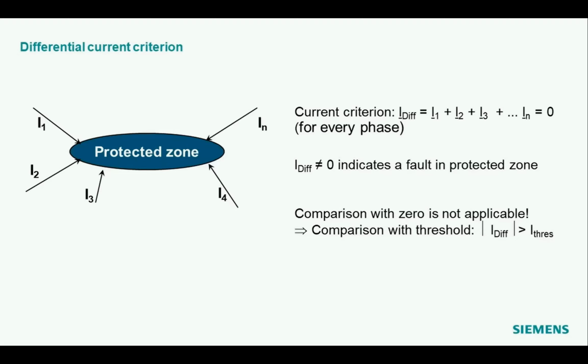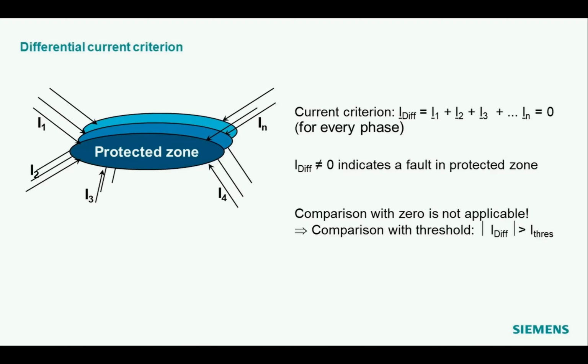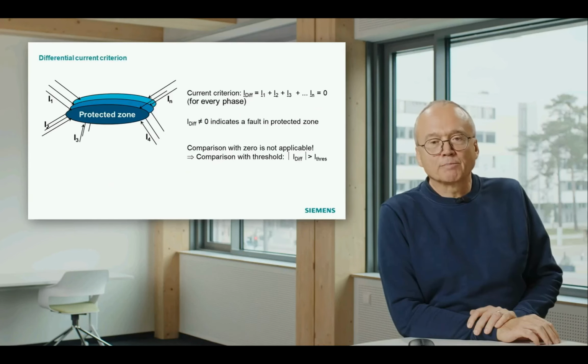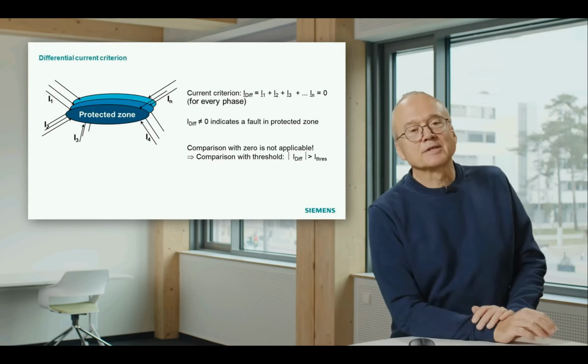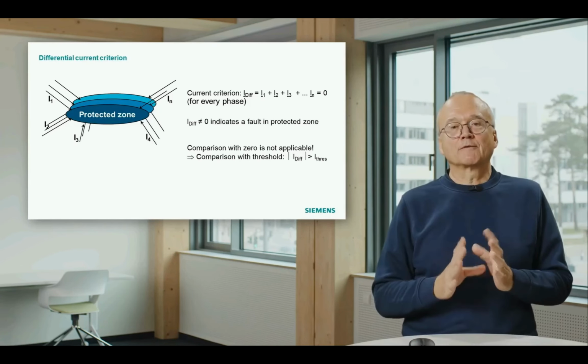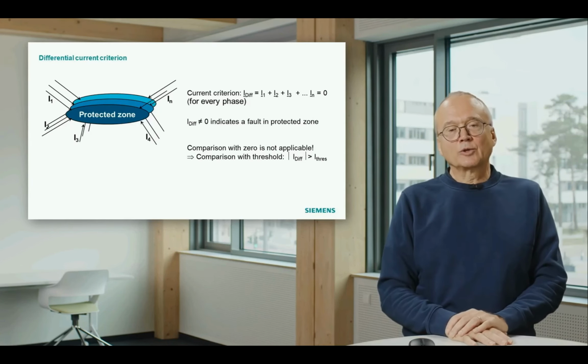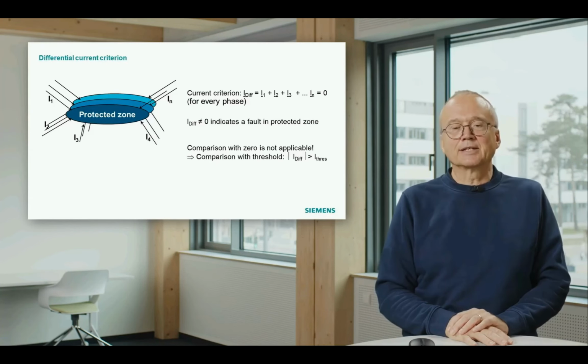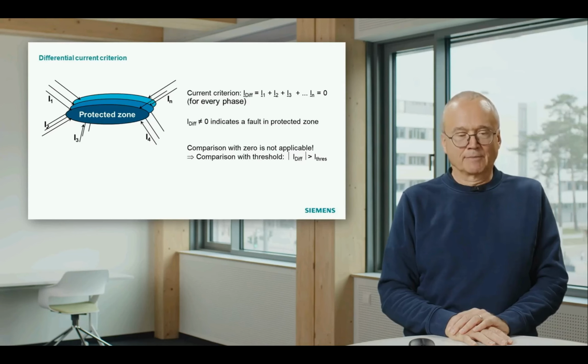And that is indicated here. That means you draw a circle around the protected zone. The protected zone can be a line, a transformer, a bus bar. You measure all the currents and you sum up the currents. Do that individually for all three phases. And in normal operation, this sum should be 0. And if this sum of the currents, we call this sum the differential current, is unequal to 0, then it is an indication that there is a fault on the protected line.